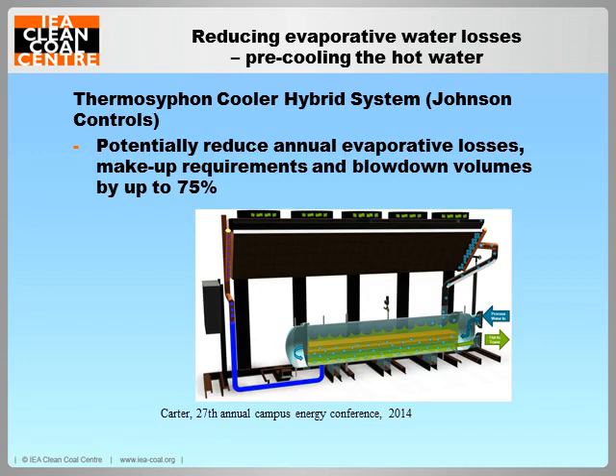Pre-cooling the warm water exiting the steam condenser before it enters the wet tower reduces the heat load in the tower and hence evaporative water loss. In the thermo-siphon cooler hybrid system, which is shown here, the heat from the hot water leaving the steam condenser is transferred to a refrigerant in the evaporator and then to the ambient air in an air-cooled condenser. There is no water evaporation. The naturally recirculating refrigerant operates in a closed loop. The system could potentially reduce annual evaporative water losses, make-up water requirements and blowdown volumes by up to 75%. And it could be retrofitted to existing power plants.